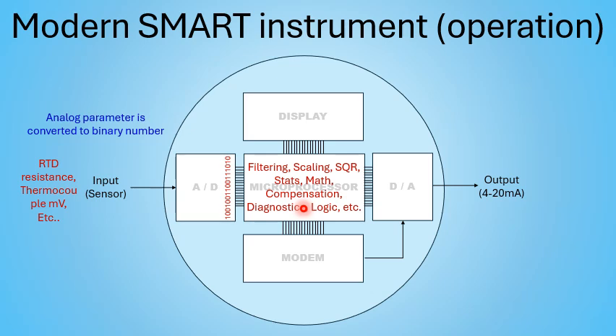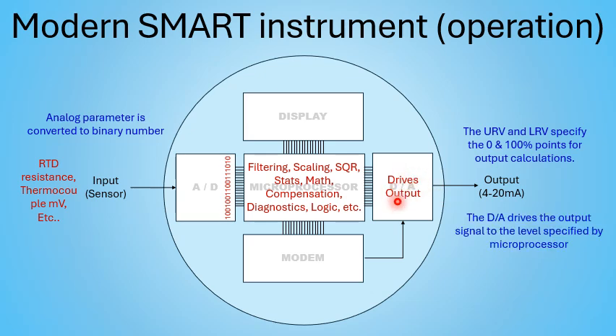If you've never read the Rosemount 3051 manual, you owe it to yourself to read that. Your mind will be blown at all the things it can do that you're probably not doing at your plant. Along with that, the microprocessor will look at the upper range value and the lower range value that you specified. Those are the 0 and 100% points, and it determines what percentage that output should be at. And it'll send that signal to the output, the D to A, the digital to analog, which we typically call the output, which will actually adjust the 4 to 20 milliamp signal.